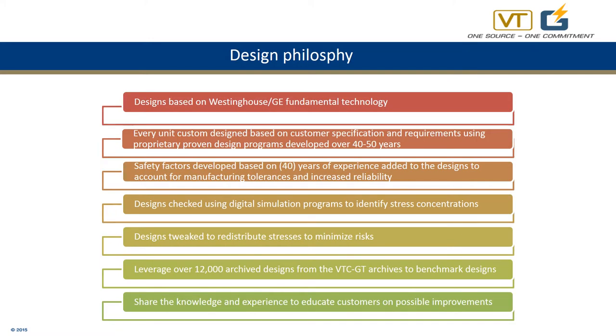We're going to conclude our presentation with our design philosophy. Westinghouse and GE are the pioneers of power transformers, and our designs are based on these two fundamental technologies. Every unit is custom designed based on customer specification and requirements, using proprietary design programs. After the initial design, safety factors are added to account for manufacturing tolerances, and more importantly, to minimize the risk of failures. These safety factors are based on over 40 years of experience. Overcompensating results in inefficient, expensive designs, while going the other way increases the risk of failures.